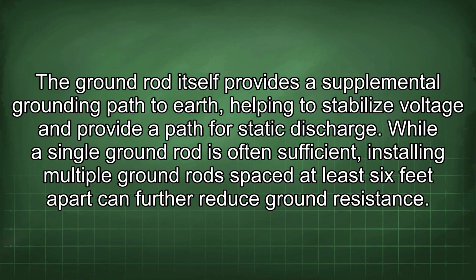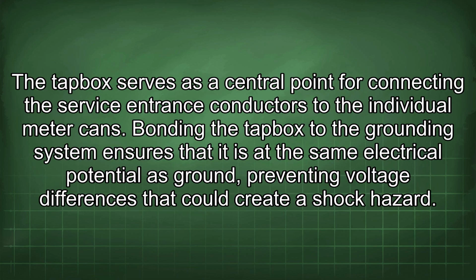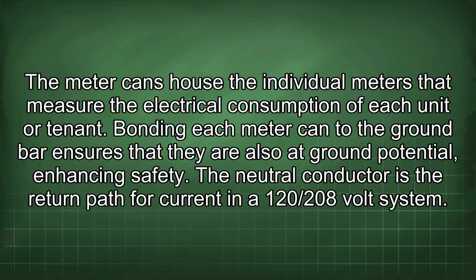While a single ground rod is often sufficient, installing multiple ground rods spaced at least 6 feet apart can further reduce ground resistance. The tap box serves as a central point for connecting the service entrance conductors to the individual meter cans. Bonding the tap box to the grounding system ensures that it is at the same electrical potential as ground, preventing voltage differences that could create a shock hazard. The meter cans house the individual meters that measure the electrical consumption of each unit or tenant. Bonding each meter can to the ground bar ensures that they are also at ground potential, enhancing safety.